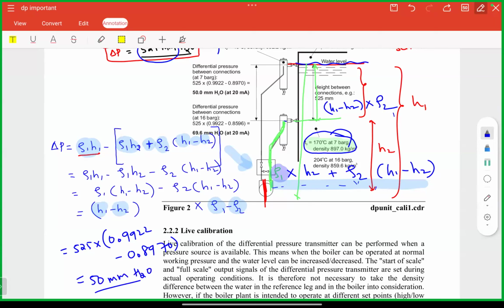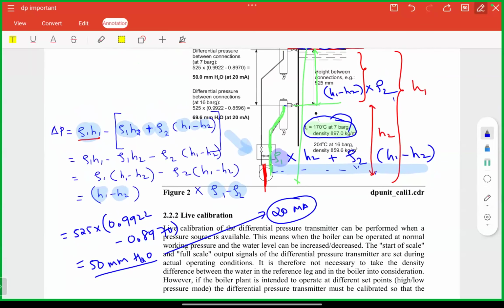Corresponding to 50 mm of water column, how much should the output signal be? 20 milliamps, high level alarm. So what will you do? You are going to apply the DP transmitter for that.